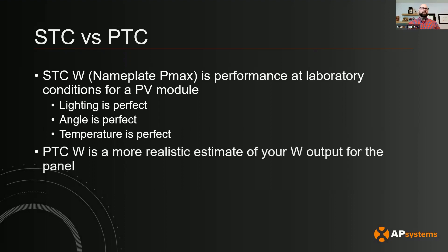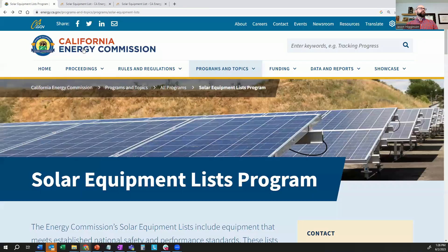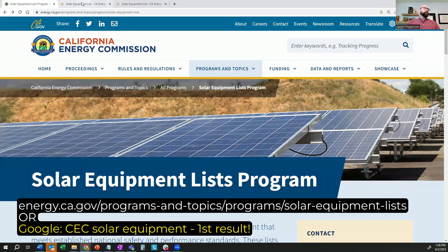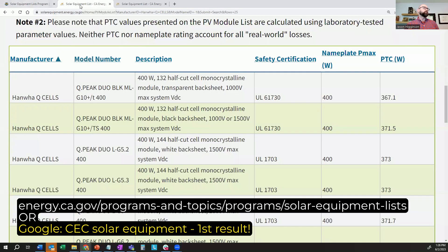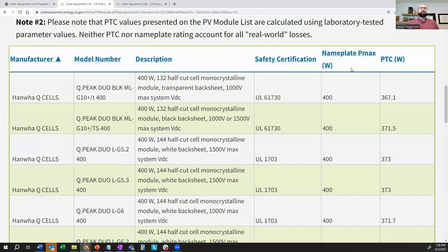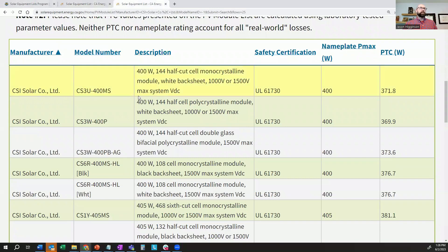In the real world it's never going to hit that, and that's really what the PTC is — that's your more realistic estimate. Sometimes they have that on the datasheet and sometimes they don't. So what you're going to want to do is go to the CEC website — the California Energy Commission — where they have their lists on all of the PV modules. You'll see here with Qcells, you'll have the nameplate wattage at 400 watts and then your PTC, which is slightly less. Same whether it's Qcells or Canadian Solar — the PTC is going to be slightly less than the nameplate. That's the difference between lab test conditions and real world test conditions.